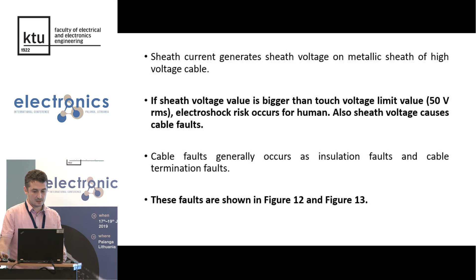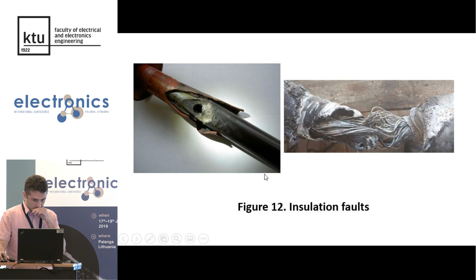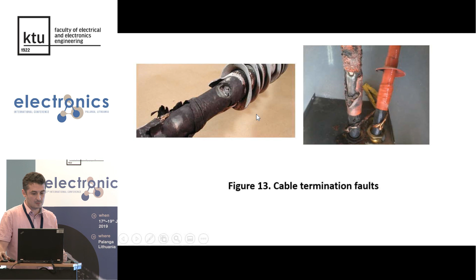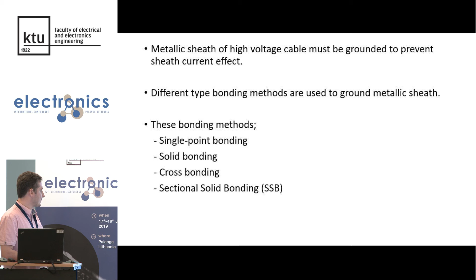Also, sheath voltage causes cable faults. Cable faults generally occur as insulation faults and cable termination faults. These faults are shown in figures. Insulation faults and cable termination faults. Metallic sheath of cable must be grounded to prevent sheath current effects. Different type bonding methods are used to ground metallic sheath. These methods in literature: single point bonding, solid bonding, cross bonding, and sectional solid bonding.